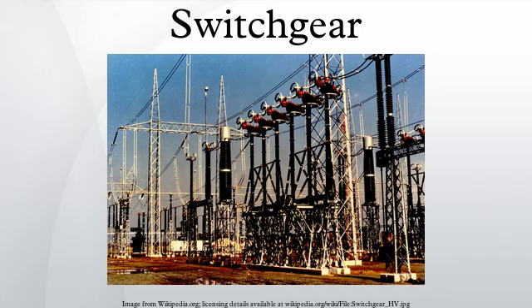Housing. Switchgears for low voltages may be entirely enclosed within a building. For transmission levels of voltage, switchgears are often mounted outdoors and insulated by air, although this requires a large amount of space. Gas-insulated switchgears used for transmission-level voltages save space compared with air-insulated equipment, although the equipment cost is higher. Oil-insulated switchgears present an oil spill hazard. At small substations, switches may be manually operated, but at important switching stations on the transmission network all devices have motor operators to allow for remote control.